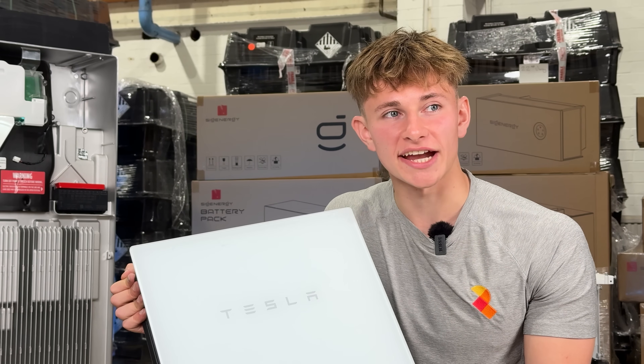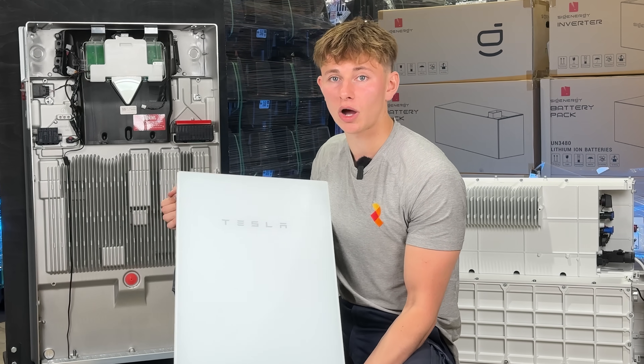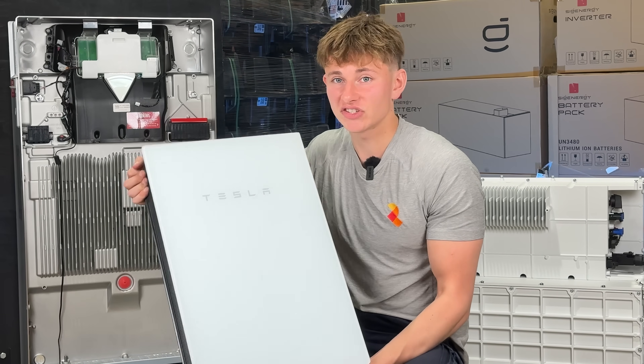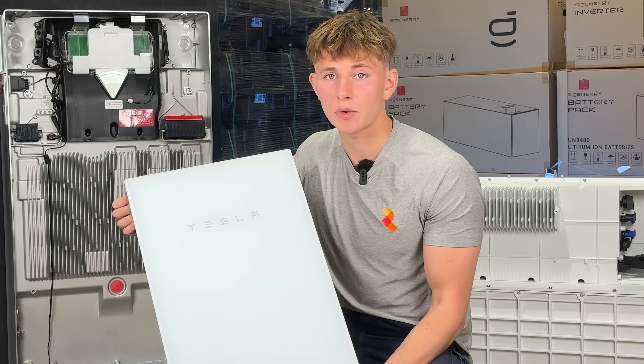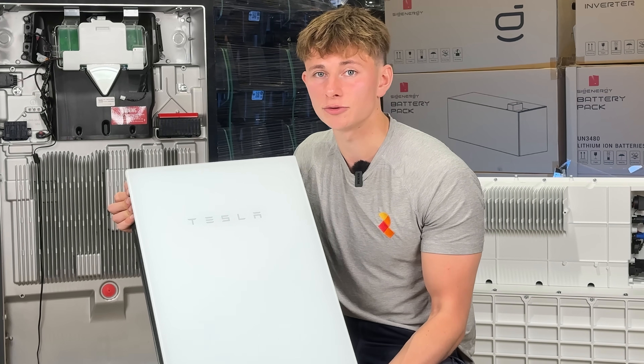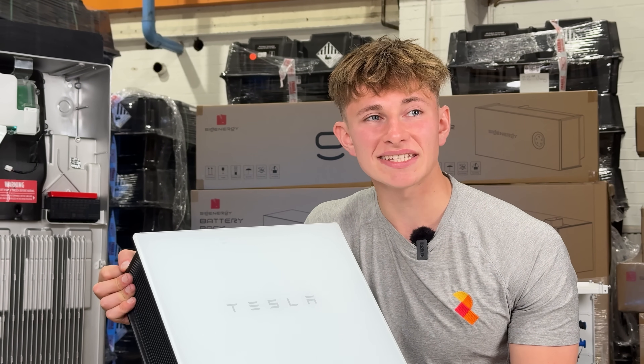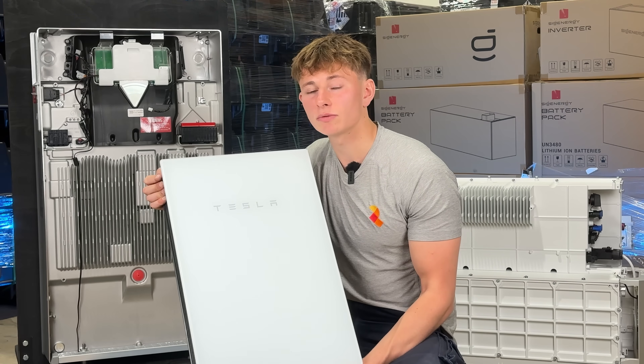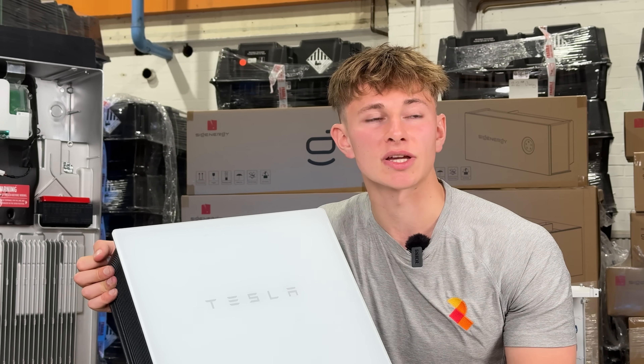Next, let's talk about power cut protection. Both systems can be installed without this, however if you would like power cut protection, additional hardware is required. For Powerwall 3, you need something called the Tesla Gateway. And for SIG Energy, you need the SIGEN Gateway. Both systems can keep a full single phase supply running in a power cut. SIG Energy can also back up three phase supplies, which is something that Tesla can't yet do — but Tesla are working on releasing a system that does three phase backup. On installation, the property's incoming supply is wired through the gateway, and if the grid goes down, the gateway can cut the supply to and from the grid and island the house, meaning the battery and the solar can keep the house running.